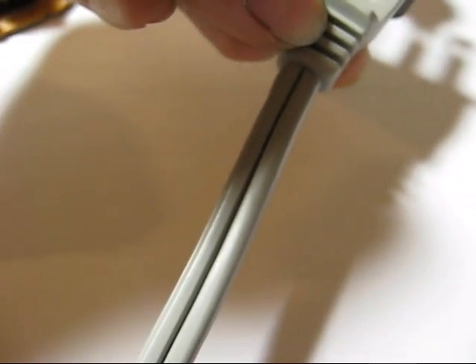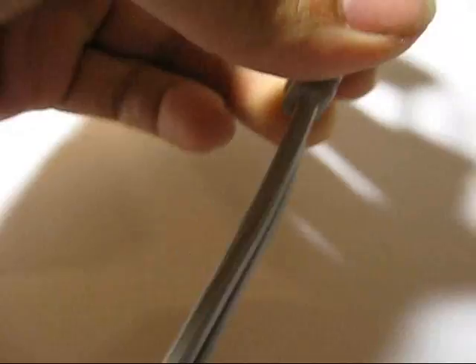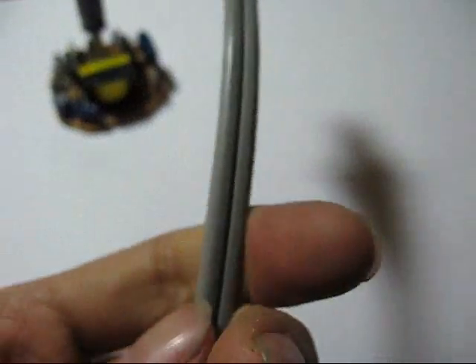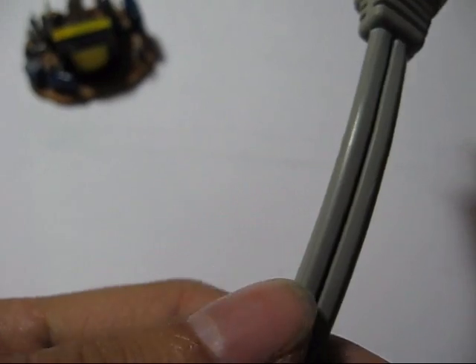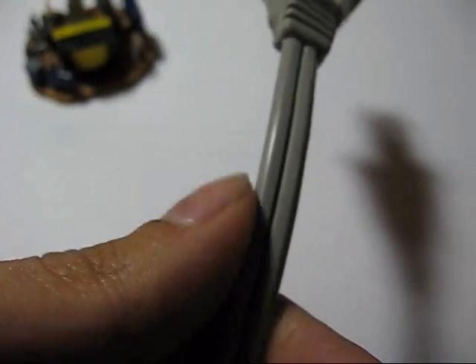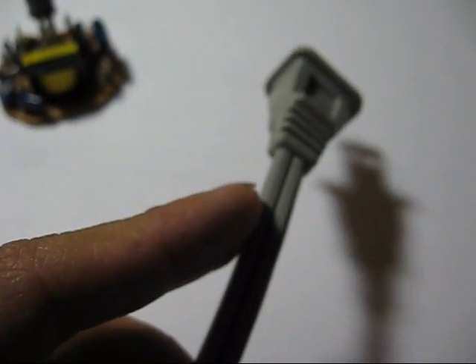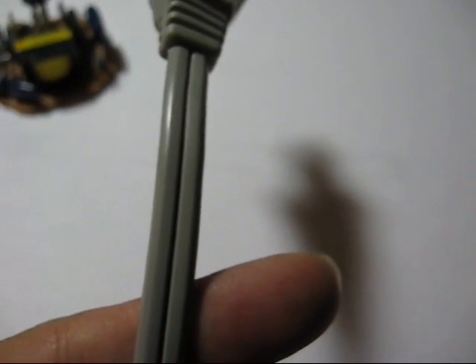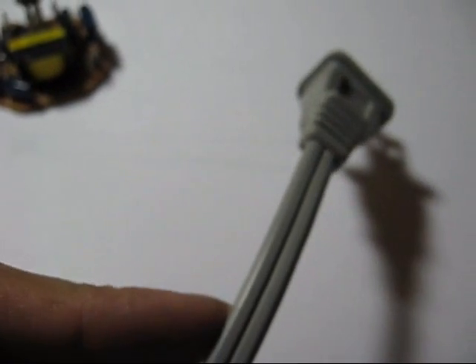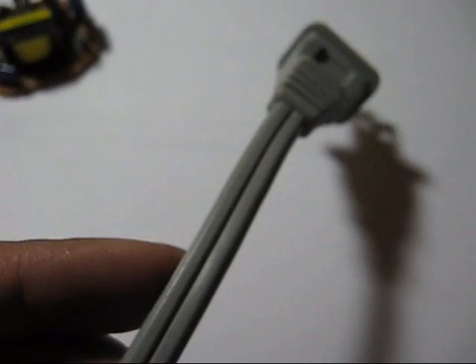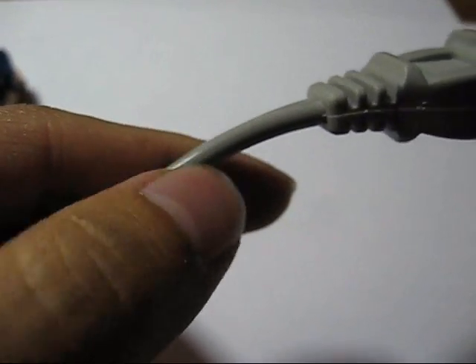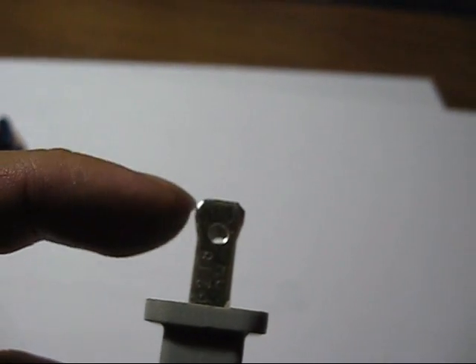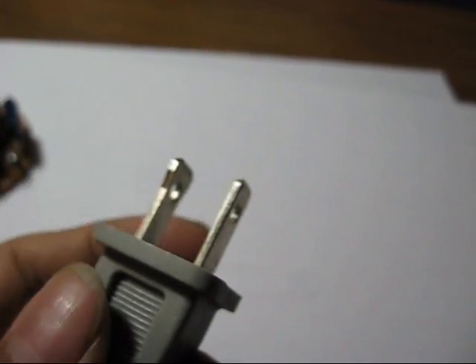So now let's take a look at one of these two prong plugs. You have two wires if you're looking at it closely. It's called a zip cord. Now the neutral wire on a cord like this is always the one that's identified. In case of this, there's actually ridges. I don't know if you can see them or not, but you can actually feel them if you run your thumb across the cord like that. That's your neutral wire. Neutral's always identified on a cord like this. And it could be ridges like this case, or in another case, you might see a white stripe, that would be like the cord on my TV, or there would be writing on it. Although some writing, if there's ridges on it, the writing might be on the hot wire, which is the smooth one. Another thing to keep in mind is neutral is always the wire that's connected to the wider of the two blades. Hot is always the narrower of the two blades on a polarized cord.